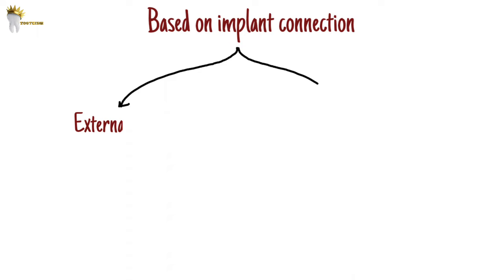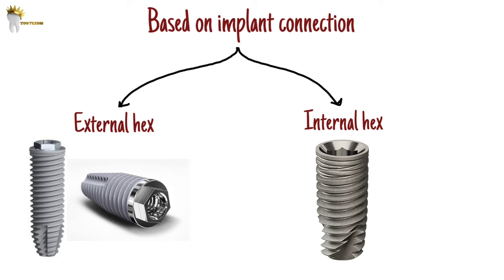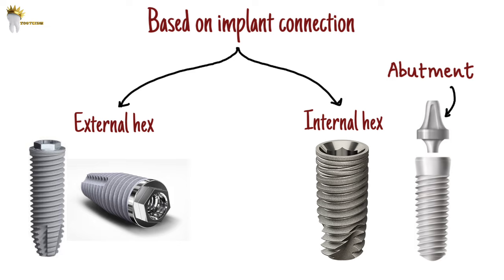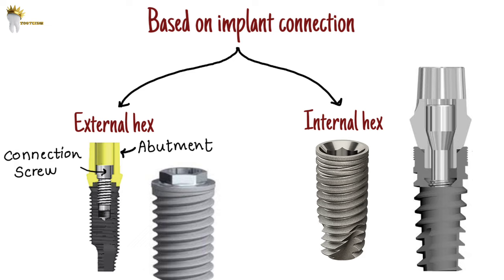On the basis of implant connection — meaning the connection of the implant with the abutment and healing screw — implants are classified as those with external connection (external hex) or internal connection (internal hex). External hex means the connection emerges above the implant platform; all components like the abutment and healing screw get engaged over and around this connection and are fixed using a connection screw. In internal hex, the connection remains inside the implant body, and all components go into the implant connection and are fixed using the connection screw.